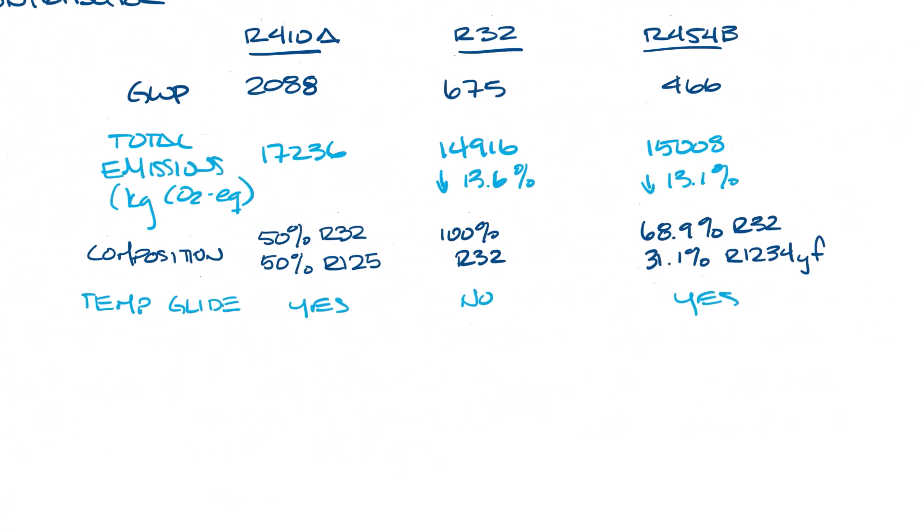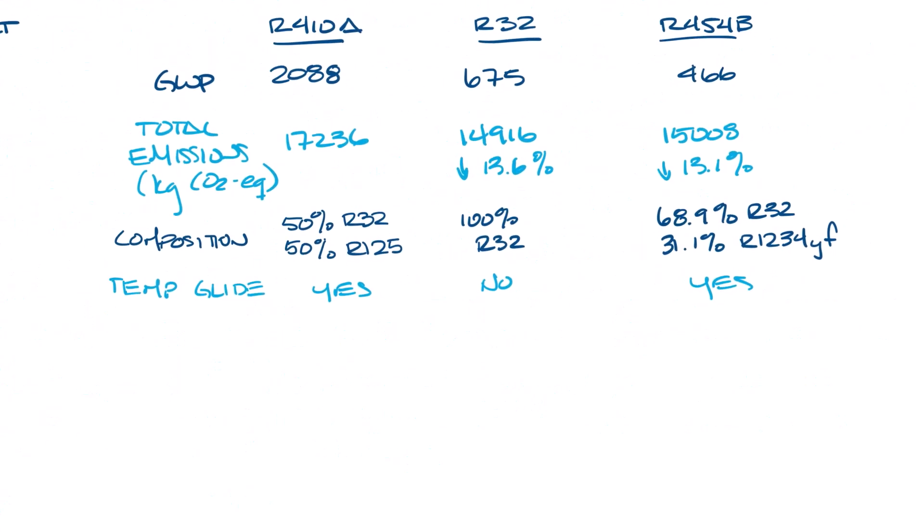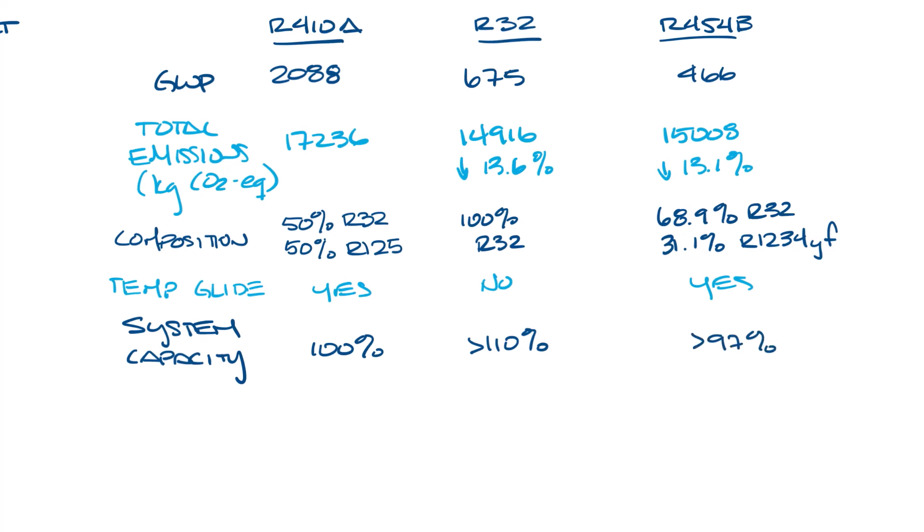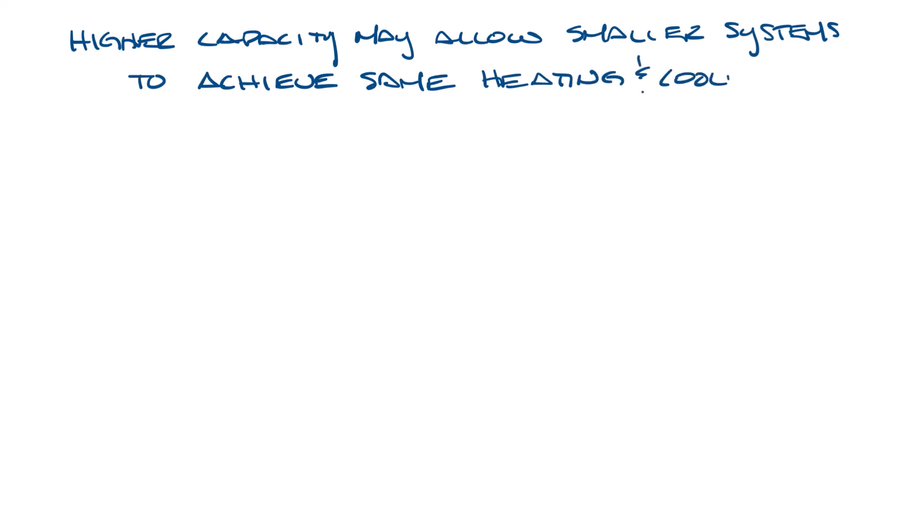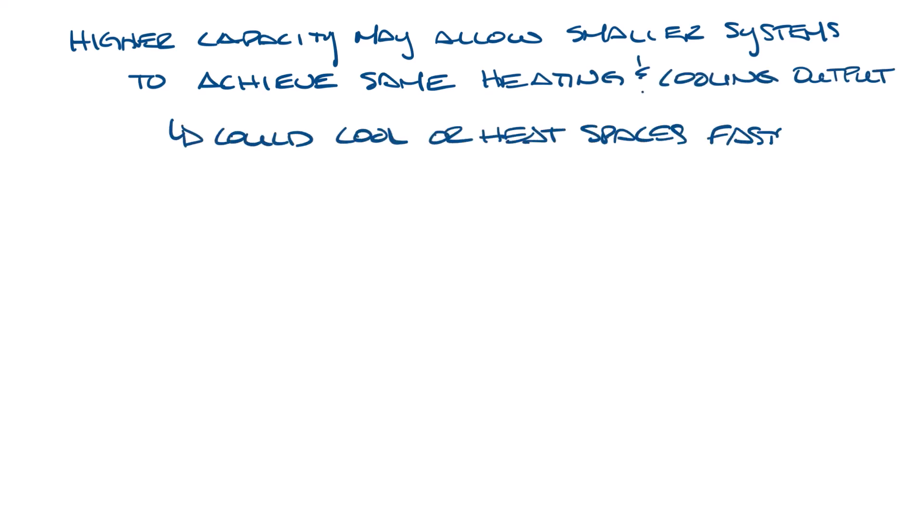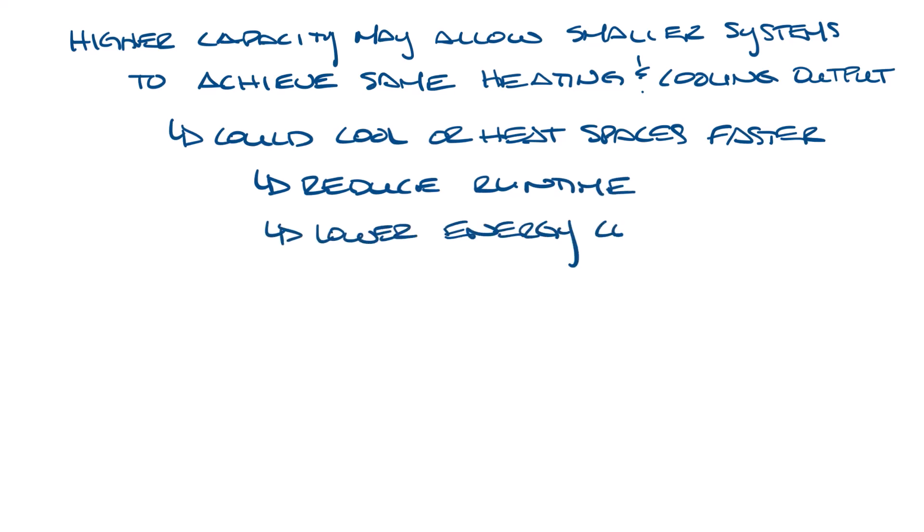Now let's go back to our table and look at system capacity. We'll use R410A as the baseline, so let's just call that 100%. R32 would have greater than 110% capacity, and R454B would have greater than 97% capacity. Let's move over here. A higher capacity may allow smaller systems to achieve the same heating and cooling output, meaning it could cool or heat spaces faster, reducing run time and potentially lowering energy consumption.